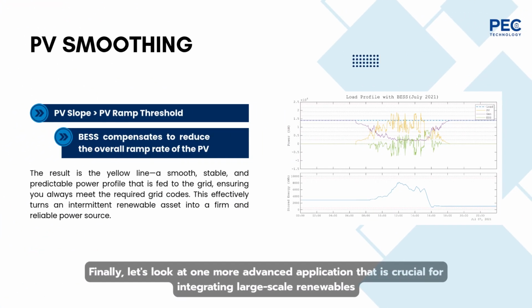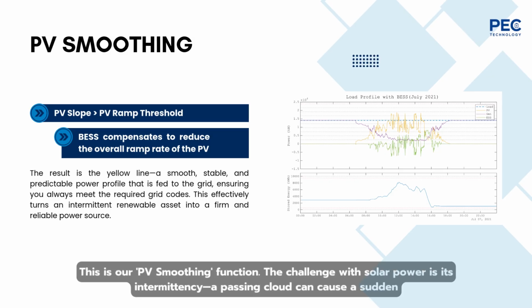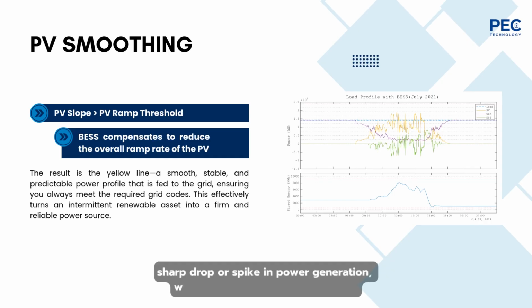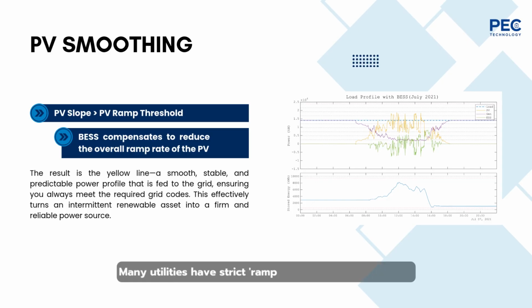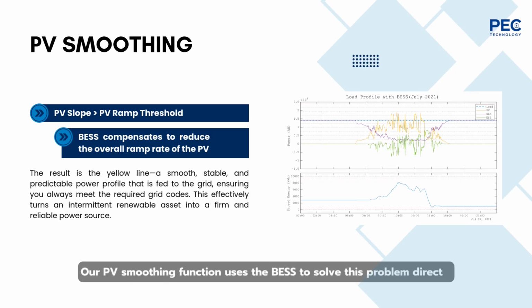Let's look at one more advanced application crucial for integrating large-scale renewables: our PV smoothing function. The challenge with solar power is its intermittency. A passing cloud can cause a sudden sharp drop or spike in power generation, which can be disruptive to the grid. Many utilities have strict ramp rate limits to prevent this. Our PV smoothing function uses the BESS to solve this problem directly.